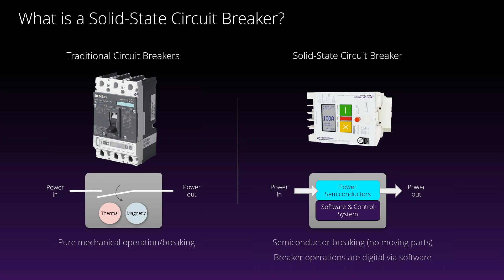A solid state circuit breaker, there are no moving parts. So you have a power semiconductor inside of there, which is controlled through a software and control algorithm through metering and monitoring of that power flow, which gives you instantaneous control on and off, the same way a computer turns on and off, the transistor ones and zeros. As soon as you see an event that you don't want to happen, you open up that semiconductor.